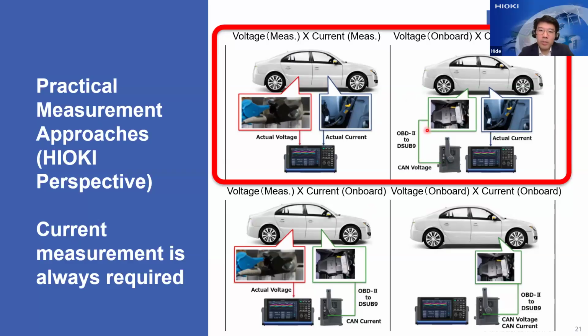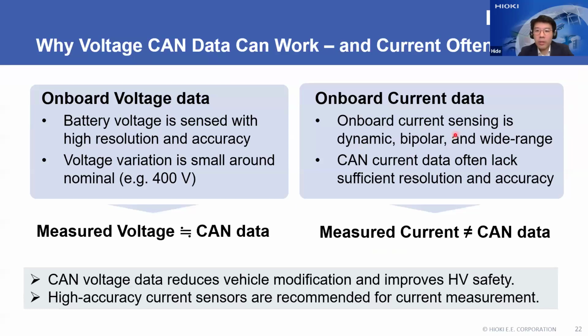Next, I'll explain why the current sensor is necessary. The standards allow 4 combinations, but current measurement should use current sensors, because onboard current data is often difficult to use for power calculation - current changes very dynamically. It's bipolar: driving produces high current, then it reduces to almost zero, and in the regenerative case the current becomes reversed.